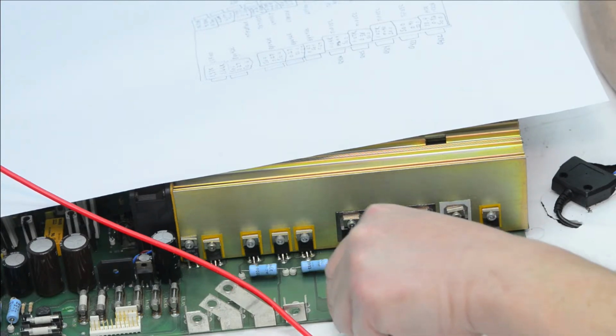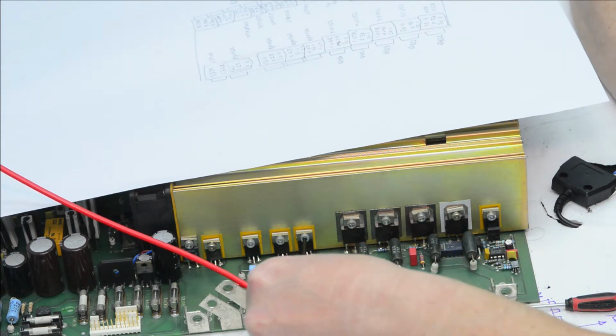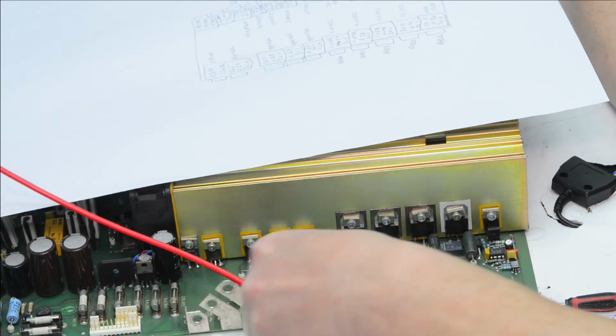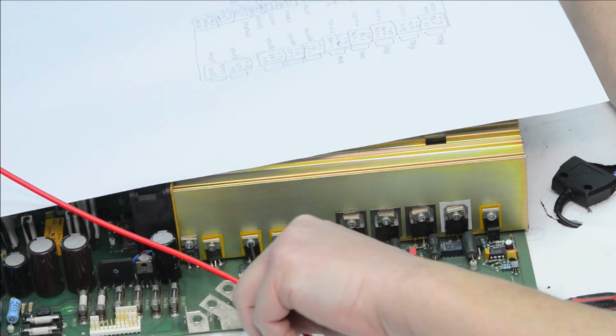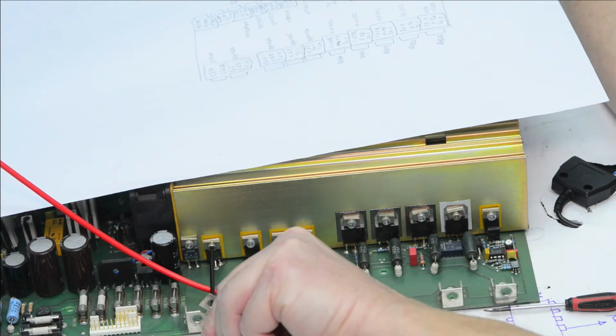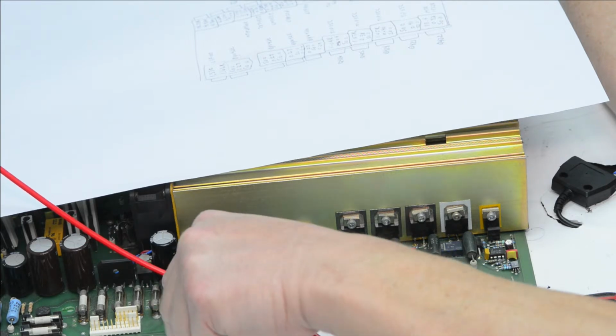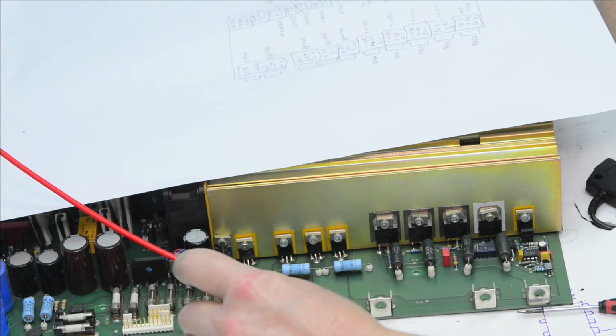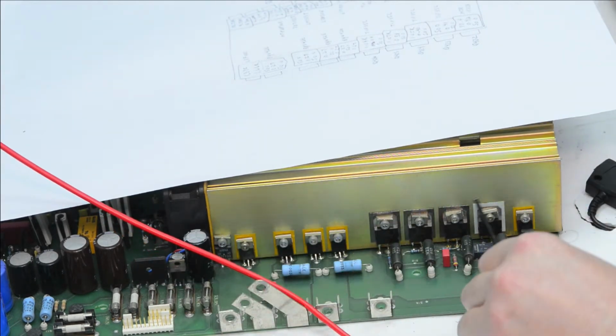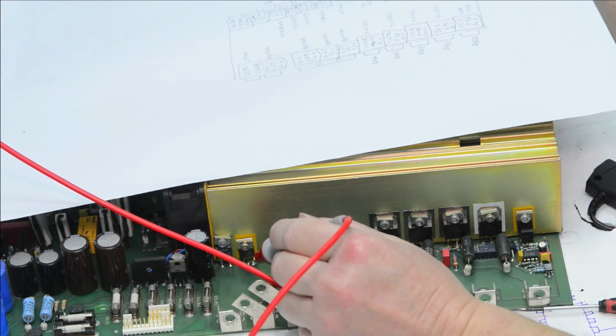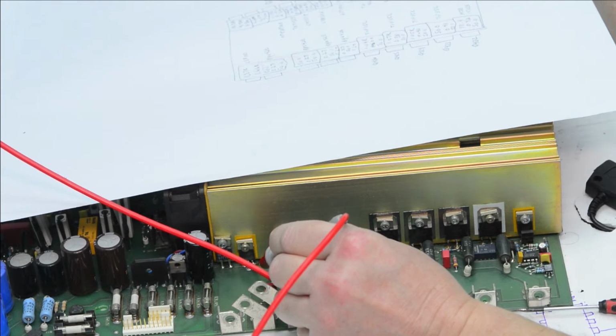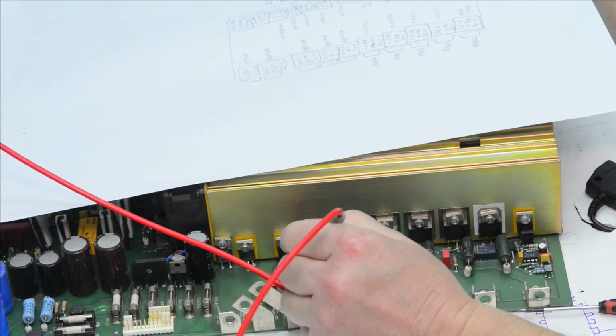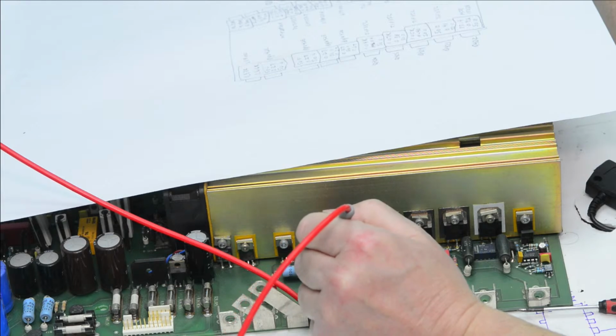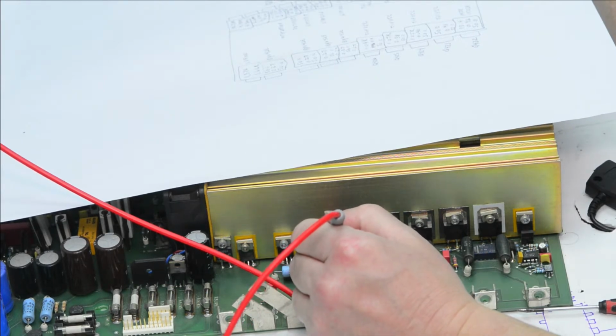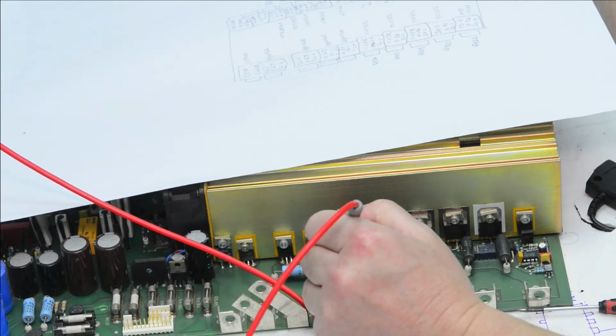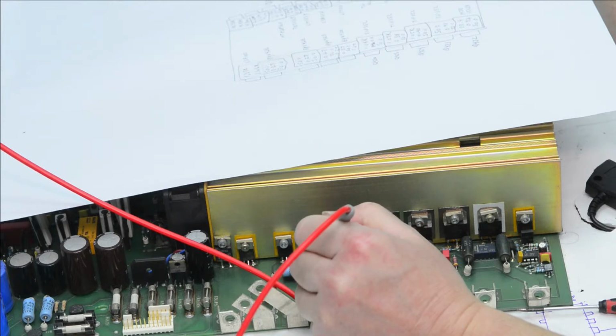This is a meetup RepairFest stream. So we are trying to repair and test an old calibrator, the Wavetek 9100, which has some power supply issues, it looks like. Some of the devices were shorted to the grounded heatsink because somebody else was already in the instrument trying to repair it before. Obviously they over-tightened the screws or misaligned them, so the tabs got shorted to the heatsink. That's what has happened in here. And we took the board out to gain access to both sides of the heatsink.